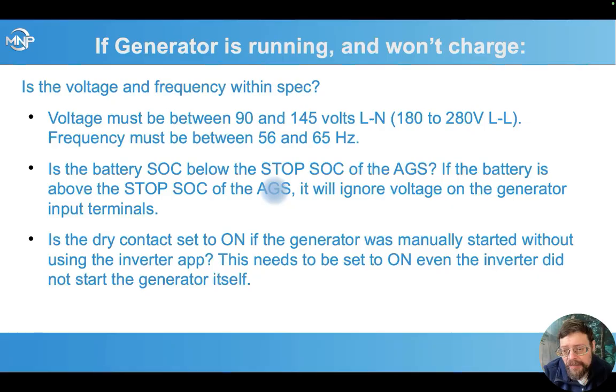So often if we have a manually started generator, we just want to set the start and stop SOC really high, like 90 and 95%, or even 90% and 100%, to make sure anytime we manually start that generator, we're going to be below that stop setting of the AGS and it's going to start charging. And checking if we manually started it, did we set the dry contact to on to let the inverter know to look for a generator on that AC or that generator input?